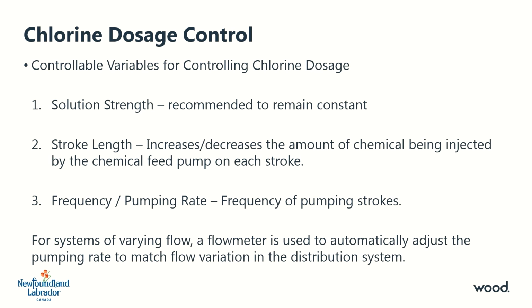Operators can adjust the quantity per stroke to increase or decrease the chlorine residual. If the pump has a frequency knob and no flow proportioning from a flow meter, then this just requires adjustment of the knob. If a flow meter is involved, then frequency adjustment would be achieved by a pulse signal or a current signal input from the flow meter.